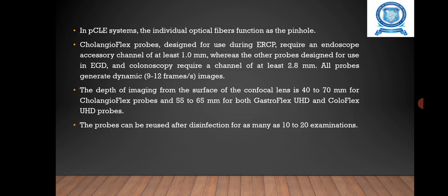One probe is designed for use during ERCP and requires an endoscope accessory channel of at least 1.0 mm, whereas the other probes designed for use in EGD and colonoscopy require a channel of at least 2.8 mm. All probes generate dynamic images.